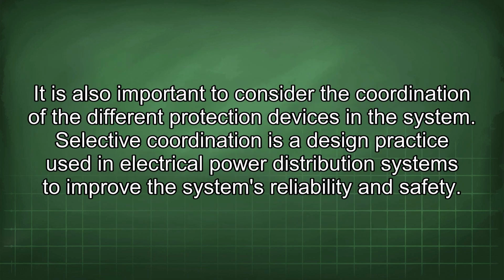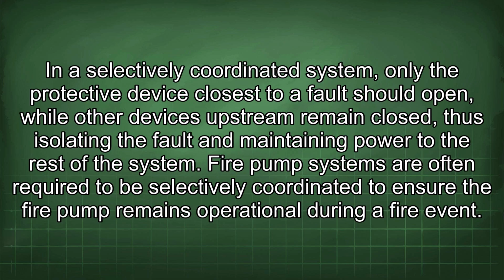It is also important to consider the coordination of the different protection devices in the system. Selective coordination is a design practice used in electrical power distribution systems to improve the system's reliability and safety. In a selectively coordinated system, only the protective device closest to a fault should open, while other devices upstream remain closed, thus isolating the fault and maintaining power to the rest of the system.